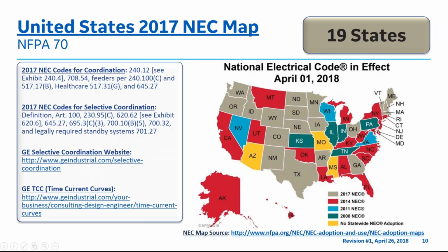Various manufacturers have public data available today, as modern technology has made it possible to selectively coordinate to 0.01 seconds for power distribution systems. Again, please check with your local AHJ about what time interval is required to meet this code requirement, as the NEC doesn't specify the time interval. It is a requirement of the consulting engineer to specify this time interval for 0.1 seconds or 0.01 seconds in their bidding specifications for the state, local, and NEC requirements. GE's selective coordination website and GE's time current curves for our devices are provided as links on the left that comply with the documentation requirements of the NEC.